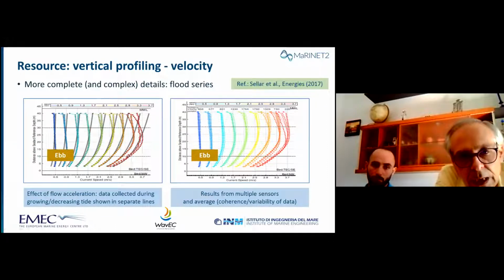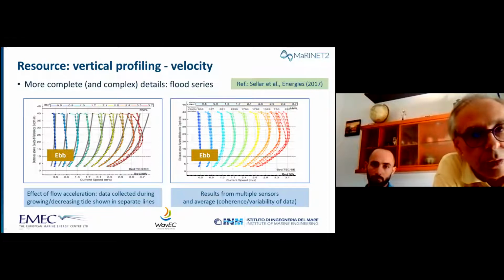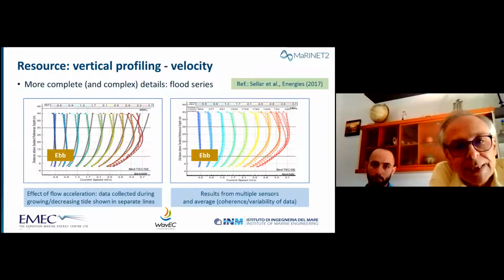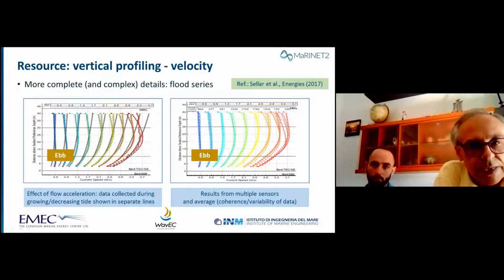Raw data measurements should always be accompanied by other data that better characterize what was happening in a general sense during the measurement, because it's very important in order to understand the trends, in order, for instance, to do troubleshooting if some measurement is apparently inconsistent because of some occurrence during the measurement.